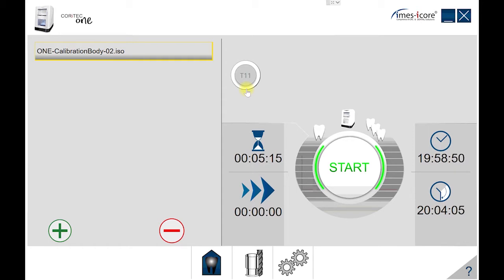After you insert the physical calibration block in your holder, ensure it is in the holder tight and doesn't rotate or isn't able to be pulled out. To begin the calibration, press the Start button. After your calibration object has milled out, remove the block from the holder and push the object out of the block with your finger. I would recommend pushing from the top side of the block on the corner of the object. This will ensure you don't break the side walls of the object.